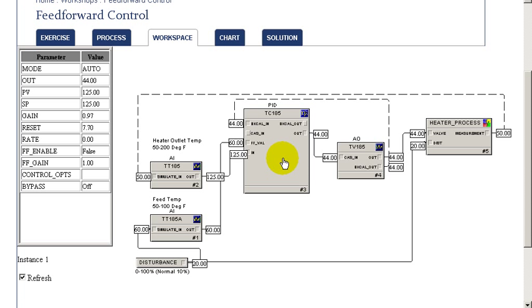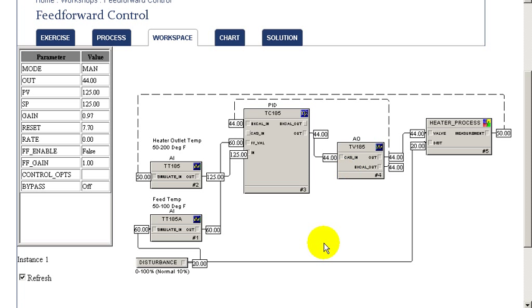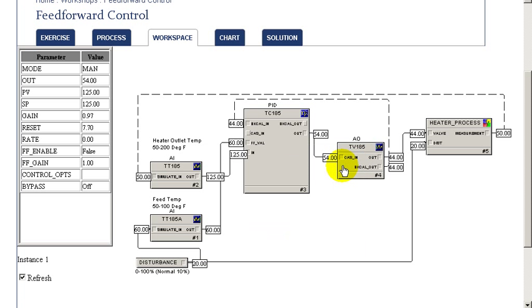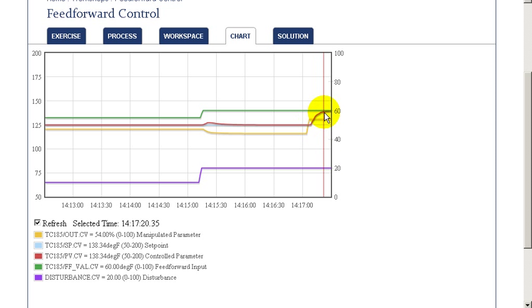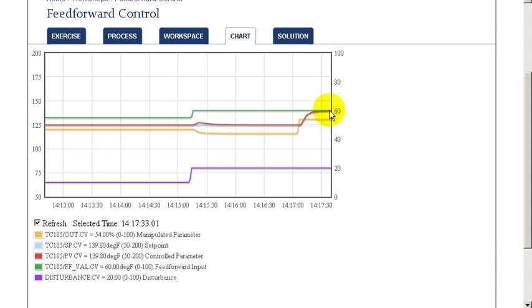We can improve the control through the use of feedforward. To do the step test needed for the commissioning of feedforward, we need to put the control into manual mode. We'll change the output of our control and examine the response of the process to that step change. In this case, we've changed the inlet steam valve by about 10%. As we can see, that is impacting the outlet temperature. Based upon the step change in our steam valve, the outlet temperature responded and eventually settles out to a new steady state value.